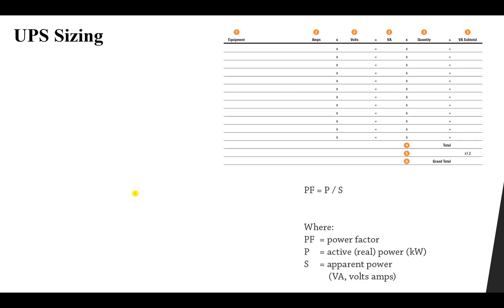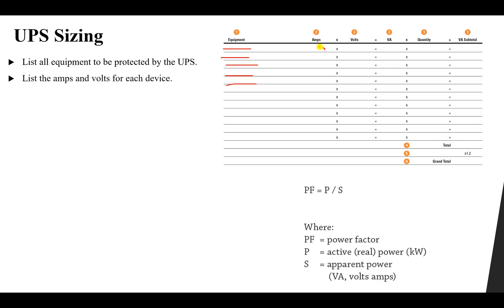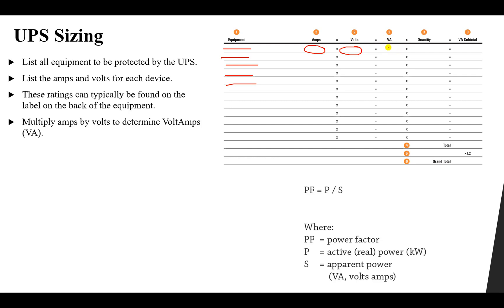Now the important question: how can we size our UPS? The first step is to list all of the equipment that are protected by or receiving power from the UPS. For each piece of equipment we note the amperes and the voltage. Multiplying these two values together gives us the volt-ampere. Our UPS is sized in volt-ampere, so we multiply current by voltage to get the apparent power.